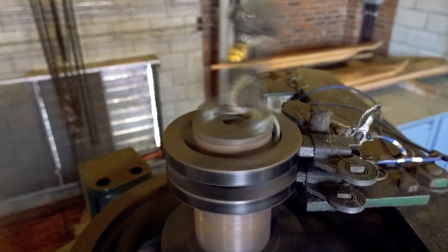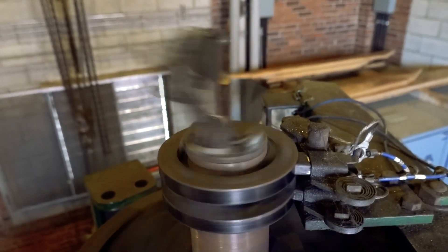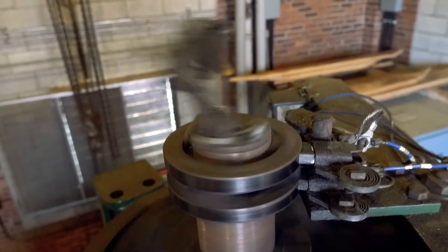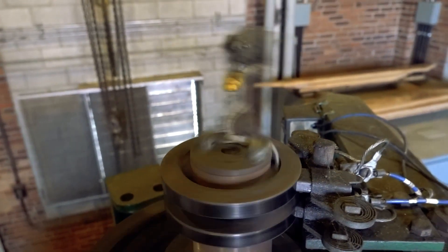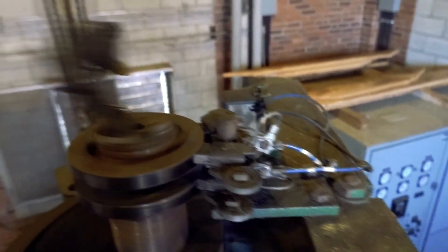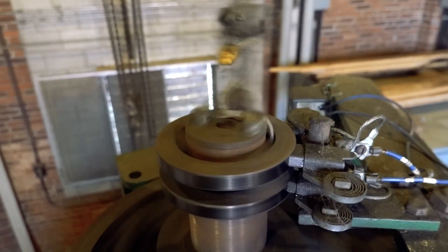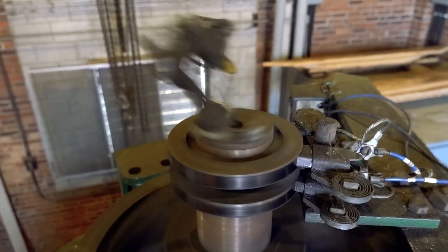That little thing right there on top — don't touch it because that dog will bite you — but that little yellow thing right there is actually the overspeed governor control. That is a mercury switch, and the little yellow bit that you see near the middle houses a single drop of mercury. If this spins too fast, it flings the mercury up into the end and closes a circuit, which goes down a couple wires here and tells the turbine to shut down. It basically starts closing wickets and doing all kinds of cool stuff, but it shuts the turbine down if it spins too fast.